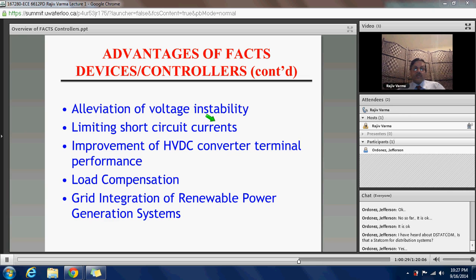And limiting short circuit currents. Now, I know in Ontario, short circuit currents are a major issue in the GTA. This is because the breakers are already at their limit of the short circuit current that can flow in that region. And we are trying to have more power flowing in the lines, which is coming from renewable energy sources or because of other conventional sources. So during a fault, the level of short circuit currents has gone beyond the capacity of the breakers, and it can cause big issues. You have to upgrade all the breakers at an enormous cost, and short circuit currents need to be restricted to be able to connect more, to be able to have a safe system. And FACTS devices can help in limiting the short circuit currents.